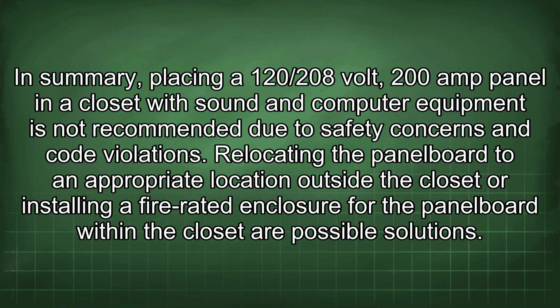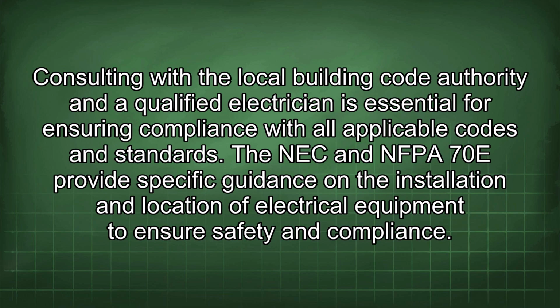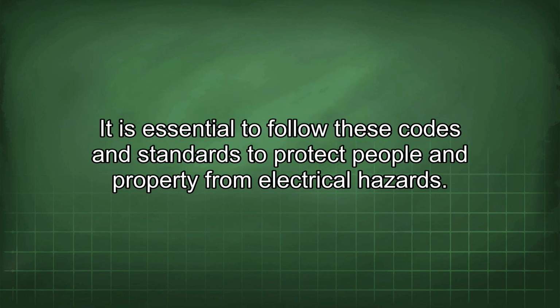In summary, placing a 120/208 volt 200 amp panel in a closet with sound and computer equipment is not recommended due to safety concerns and code violations. Relocating the panel board to an appropriate location outside the closet or installing a fire-rated enclosure for the panel board within the closet are possible solutions. Consulting with the local building code authority and a qualified electrician is essential for ensuring compliance with all applicable codes and standards. The NEC and NFPA 70E provide specific guidance on the installation and location of electrical equipment to ensure safety and compliance. It is essential to follow these codes and standards to protect people and property from electrical hazards.